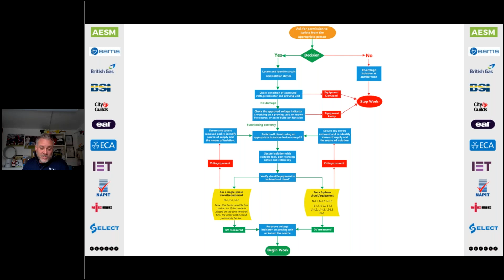And then we're going to verify. We're going to verify that those points are dead. And again, we do that using our approved instrument. And importantly, once we've verified that the line conductors, the neutral, and the CPC are proved dead, we're going to retest our proving unit to make sure that it hasn't failed during that operation. And that circuit's successfully isolated.